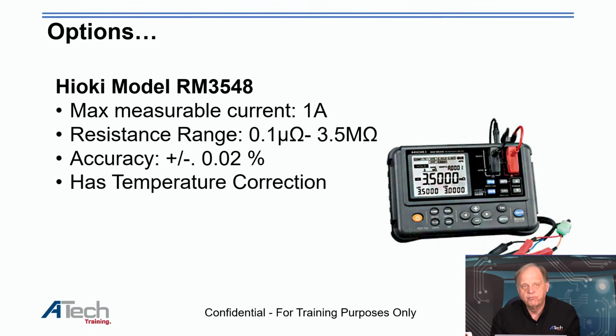It's model RM3548, measurable value, again, for current's 1 amp. They're pretty much all going to be that. The resistance range on it is 0.1 micro ohm up to 3.5 megohms. This thing's got a pretty strong range on it and has an accuracy of plus or minus 0.02. That's pretty good. It does have temperature correction, so that makes it a little bit better on the meter. This is one that I think Toyota recommends for their procedures and testing. So if you work on a lot of Toyotas, this might be a meter that you want to look at so it matches the factory.